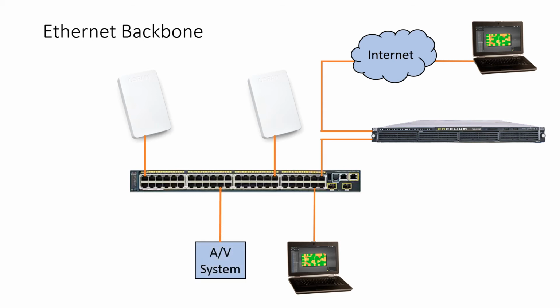If we add an optional AV interface to the SSU, then we can communicate with the AV system via Telnet over IP. Adding the optional BMS interface to the SSU allows us to speak BACnet over IP. Now we can do things like share occupancy sensor status with the BMS to enable changes to climate control based on building occupancy.